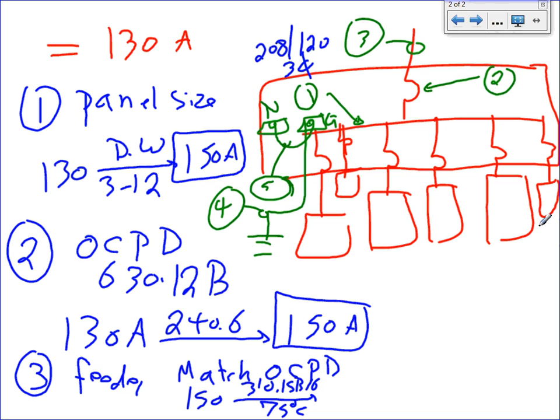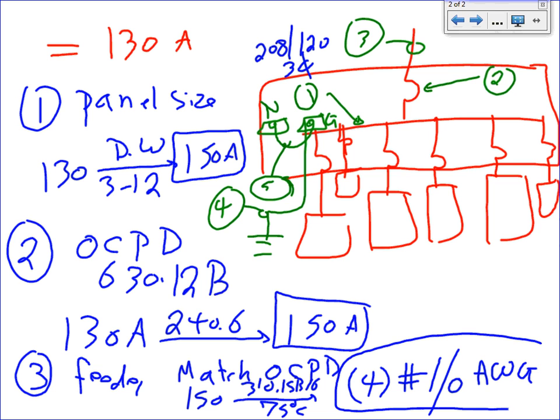How many? I'm going to pull full neutral. I'm not going to get into the neutral. Full neutral. 3 conductors plus ground neutral. So I have 4 conductors. Number 1/0 AWG. Okay, so I wired this panel with 1 aught, 4 conductors, full neutral.